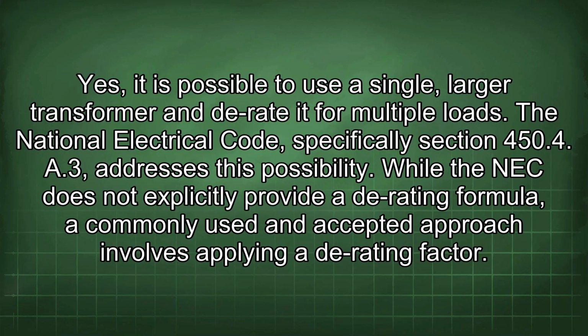Yes, it is possible to use a single, larger transformer and derate it for multiple loads. The National Electrical Code, specifically Section 450.4a3, addresses this possibility. While the NEC does not explicitly provide a derating formula, a commonly used and accepted approach involves applying a derating factor.